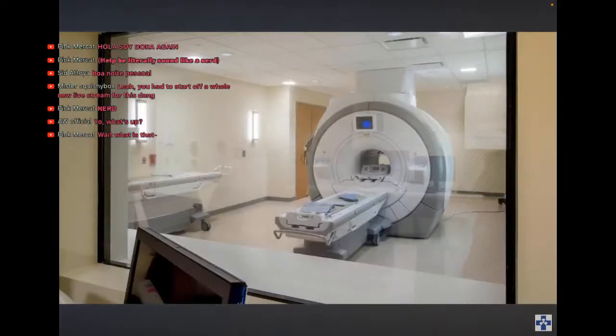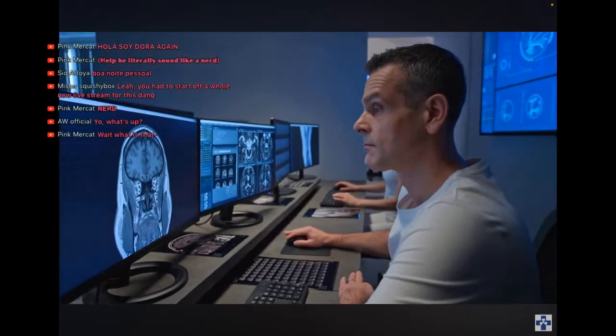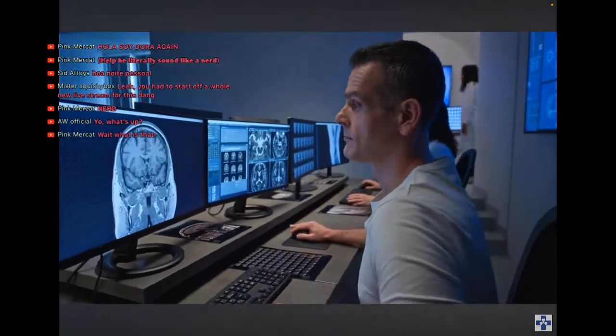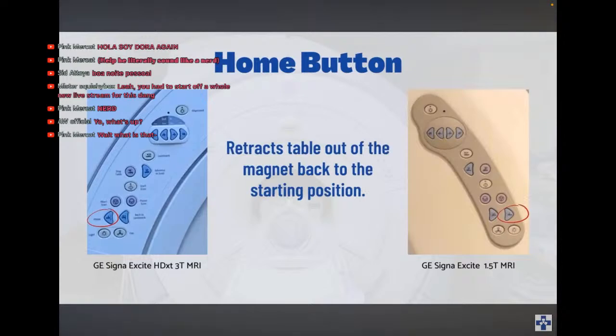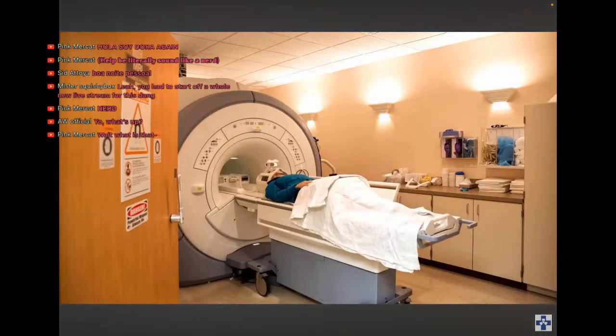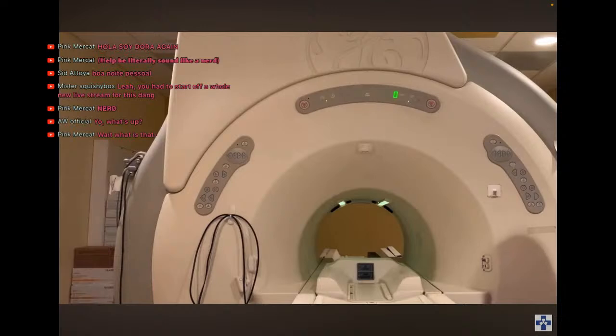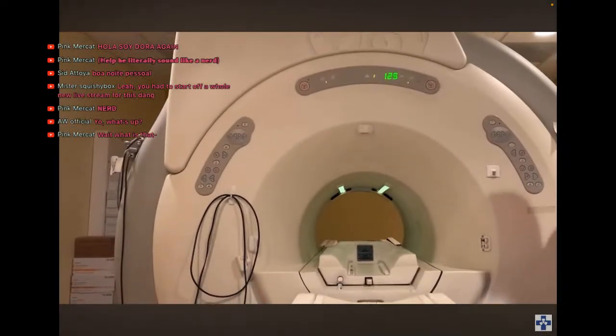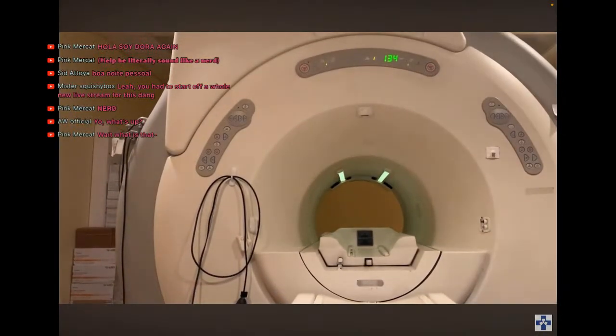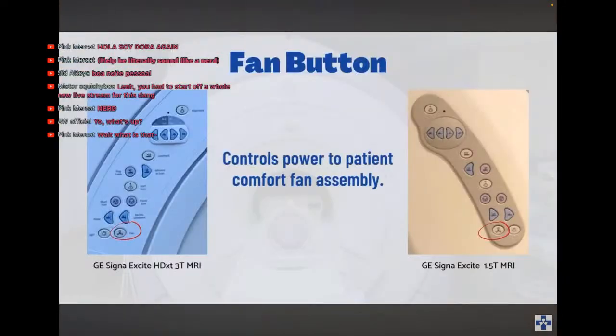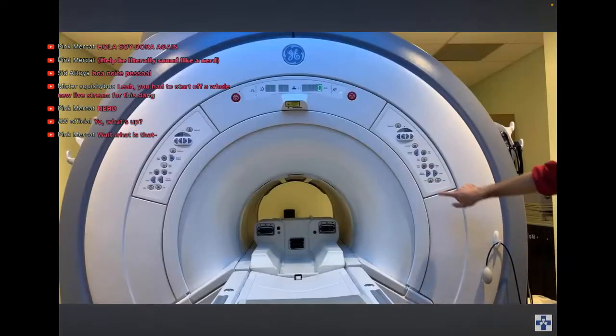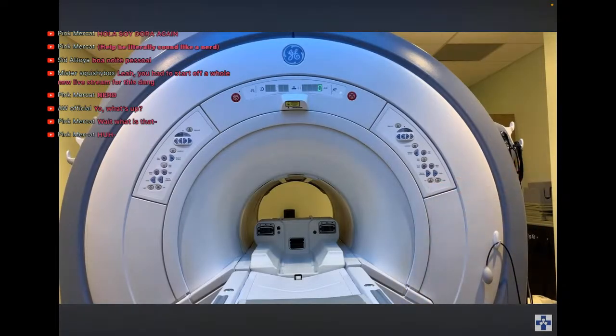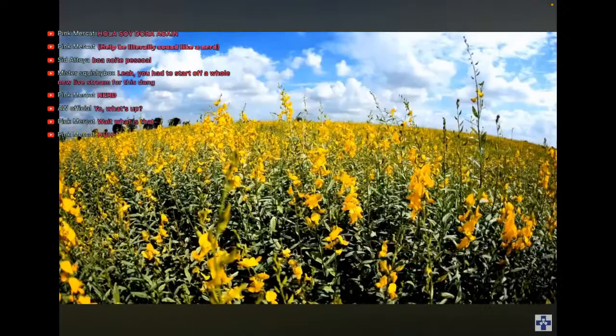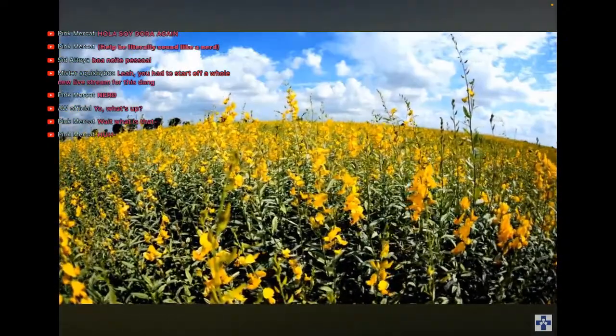Once pressed, scan functions may only resume by clicking the Start Scan button from the Scan Prescription window in the operator console. The Home button moves the patient table out of the magnet to the starting position. Once in the home position, the patient table can move up and down using the pedals located at the base of the magnet or at the rear of the patient table. The Fan button controls power to the patient cooling fan located at the rear of the magnet. Patient cooling fans provide a nice breeze to control air circulation during the MRI scan and help to reduce claustrophobia that some patients may feel. The patient fan should remain on at all times.